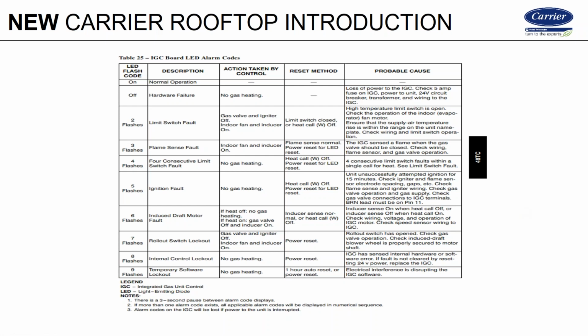This board, when you're running in the heat mode, so let's say we're running auto fan, when the board starts the system up, we're going to start the induced draft motor. We're going to look for pressure switch proving. Once that happens, then we're going to start the spark igniter, and we're going to energize the gas valve. If flame is proven, and it's flame rectification to ground, by the way, just like our furnaces, it's a microamp signal, about 0 to 5 microamp, and just like on our furnaces, 0.5 is dropout, and typically you see about 3.5 to 4 microamp out in the field when you're reading it, and it's a series reading with your meter.